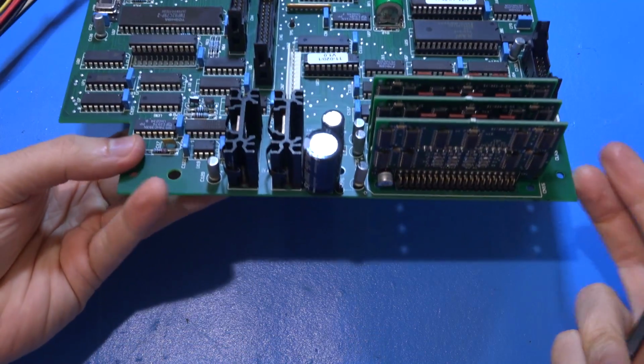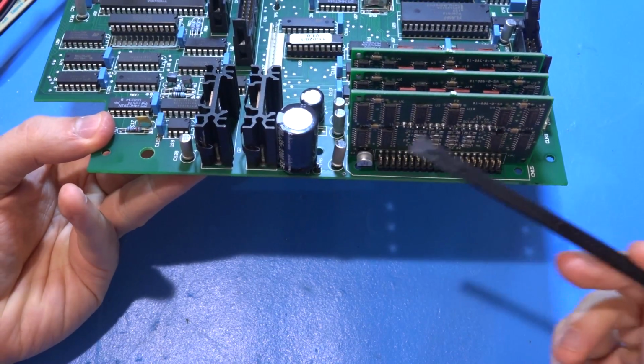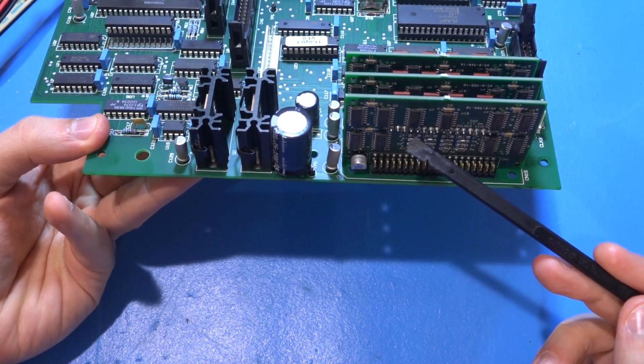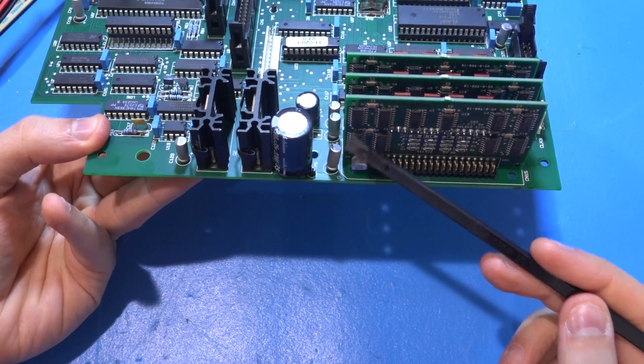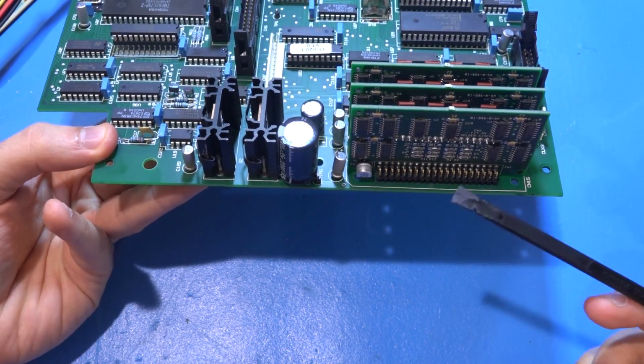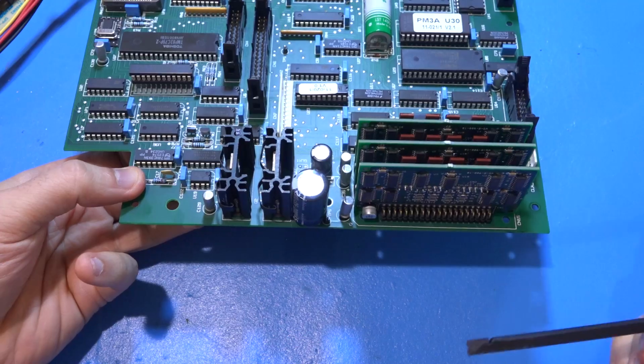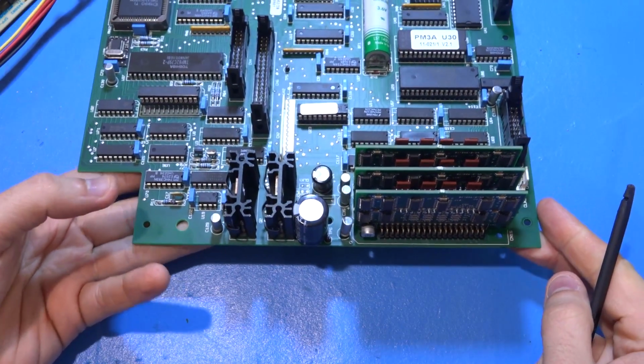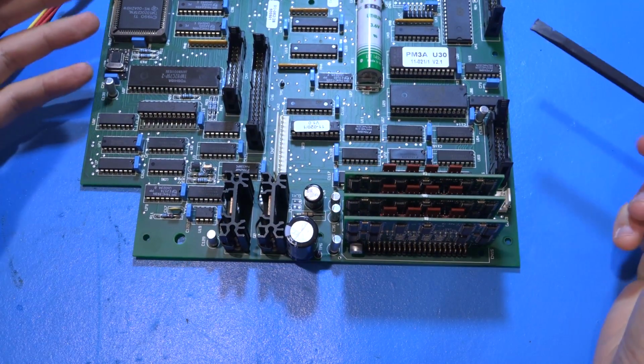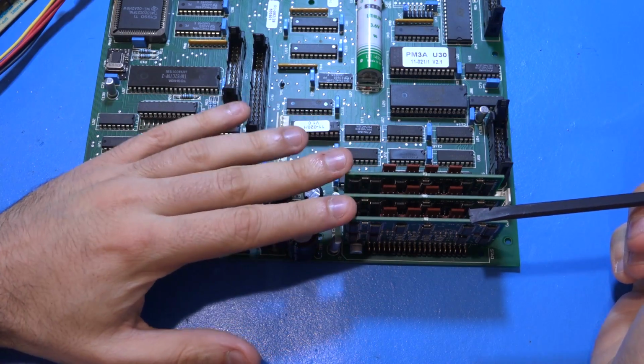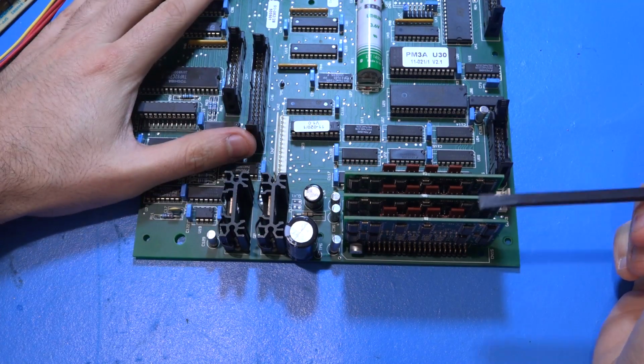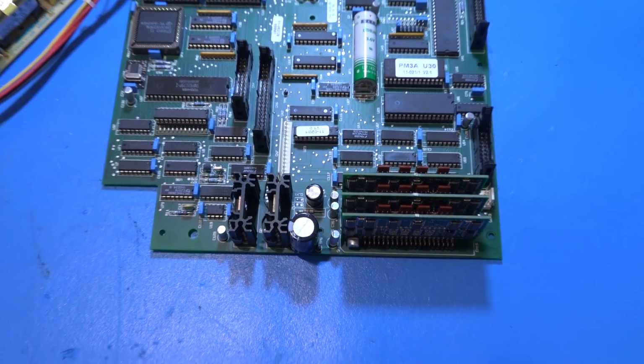So now you can also understand what the role of these boards are, because what you have is data coming from the opto-isolators and those pulse transformers, and you need to convert them back into the digital I/O configuration for the rest of this board. And that's what these boards are doing. They're essentially just converting that. Interesting design here, where wherever there is a daughter board that's surface mount, everything else is through hole, probably an older design being kind of retrofitted.